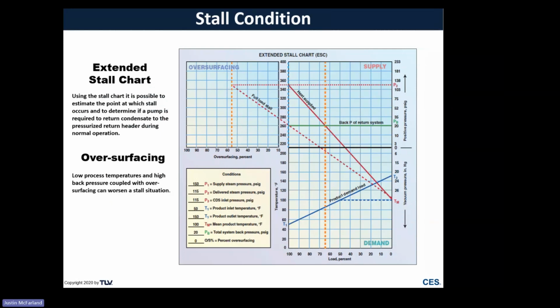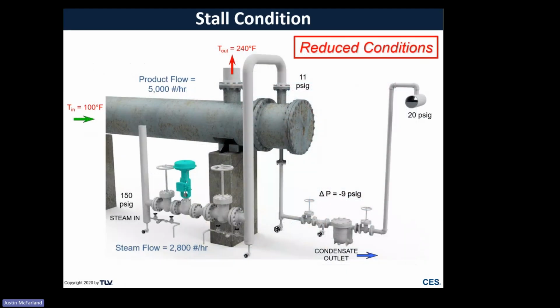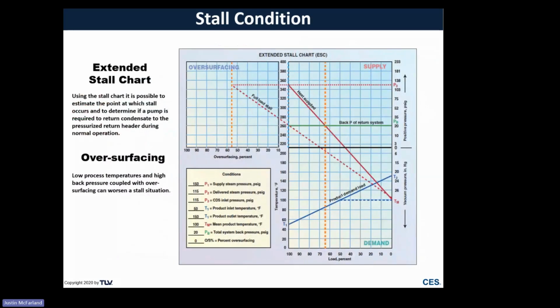So one of the things that TLV offers, it's actually a tool we developed a while back. It's called a stall chart. This is a way to look at all of these different types of scenarios, and not just your full load, normal load, and reduced load. It's a way to graphically represent everything that's happening from your worst case design load to your worst case low load scenario. And what we're able to do is plot basically all the conditions on a graph, put some lines together, and we're able to see that we have a stall point.